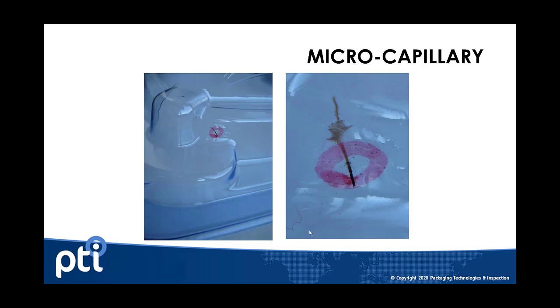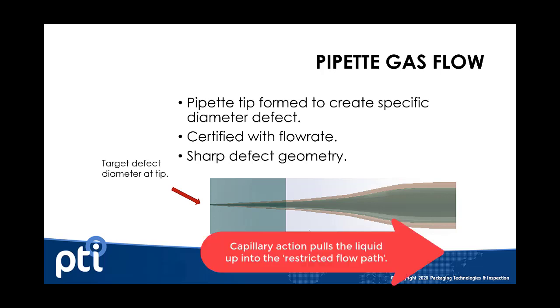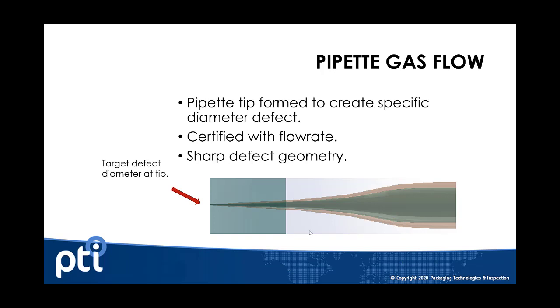Capillaries don't work as well when dealing with liquids. While you can restrict gas airflow with a capillary, the moment that capillary or pipette comes into contact with liquid, you have what's called capillary action — the liquid pulls forward up through the capillary, and that affects the overall restricted flow rate you were producing with just a gas leak. That's why a capillary is suitable for gas defects only and not liquid.